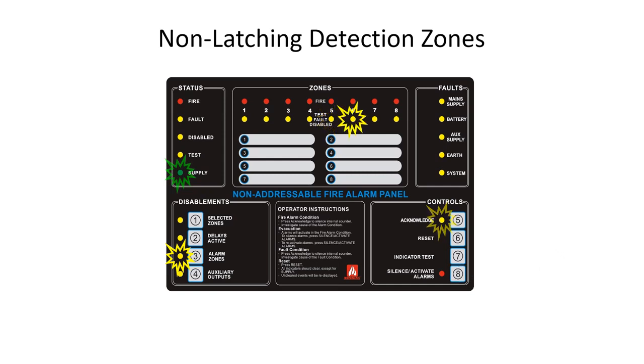Check that the relevant yellow detection zone LED is on and the acknowledge LED flashes. When the desired detection zone is selected, confirm the selection by pressing the acknowledge button. The companion red fire LED will be on. If required by the system design, repeat the process for other detection zones. When finished, press the alarm zones button to exit the non-latching zones configuration. The alarm zones, acknowledge, and fire LEDs will all be off.